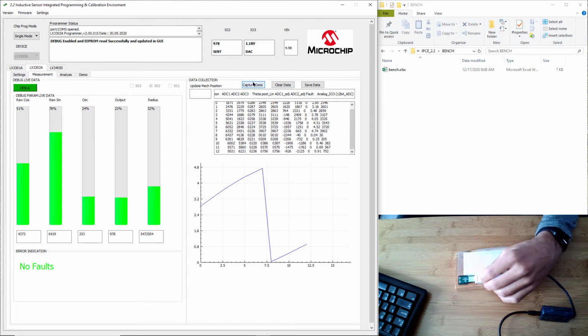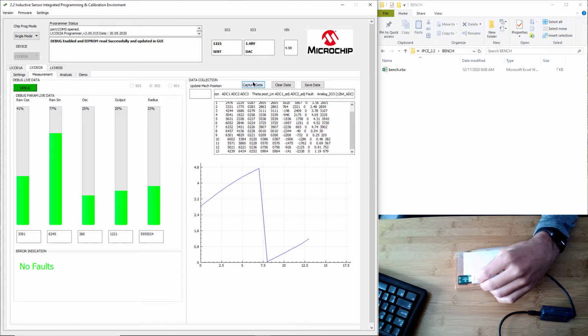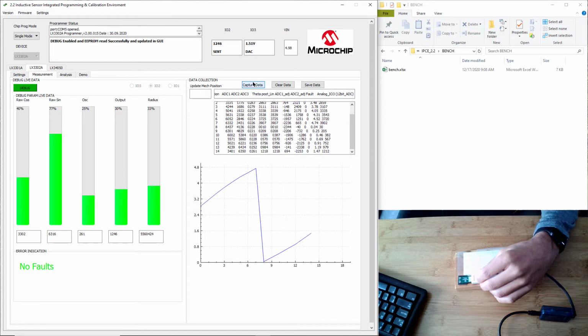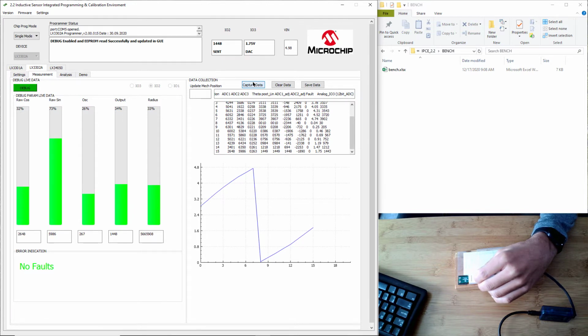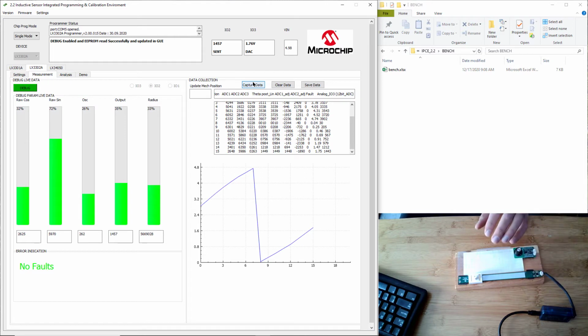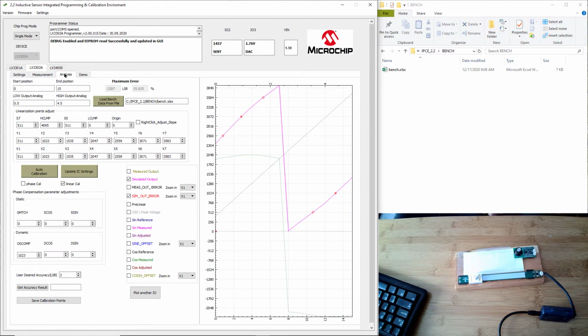Now there's going to be some error associated with this because I'm using my eye to line the target up to the graph paper. If you use calipers or a more accurate mechanical position, you'll get the best accuracy. There's also an inflection or wraparound point in the middle here. This is due to one of our calibration parameters called the origin. It's not set correctly for this linear sensor, and the auto calibration function will fix that too. So we're ready to go over to the analysis tab.